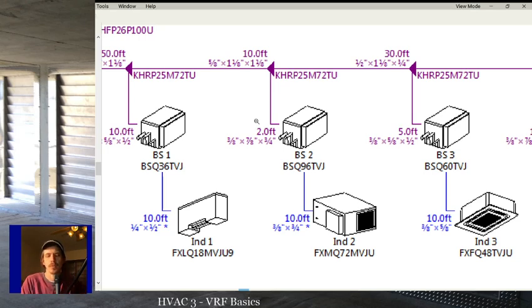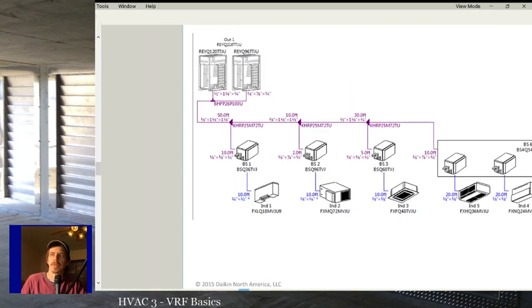And with VRF, we won't really lose the ability to get it there, but we can still cause turbulence that'll especially cause noise. Like if there's a lot of turbulent refrigerant flow up to one of these branch selectors when the solenoids are opening, you'll hear the refrigerant hissing more going through the branch box. So you want to keep a minimum distance of generally 2 feet from component to component, but you also want to keep the lines basically as short as possible outside of that to each component. So you want to give that minimum distance, but not be excessive.